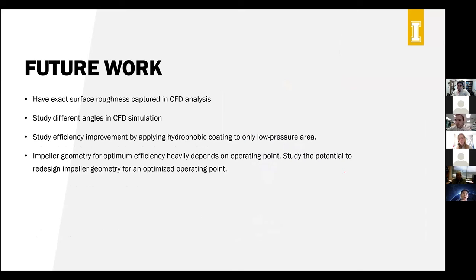So in the future, we need to have an exact surface roughness captured in our CFD work. It'd also be interesting to look at the different angles and planes in the CFD simulation itself. We'd also like to look at the efficiency improvement captured by applying a hydrophobic coating to only the low pressure areas, as well as improving the impeller geometry for the optimum efficiency depending on a new optimum operating point.